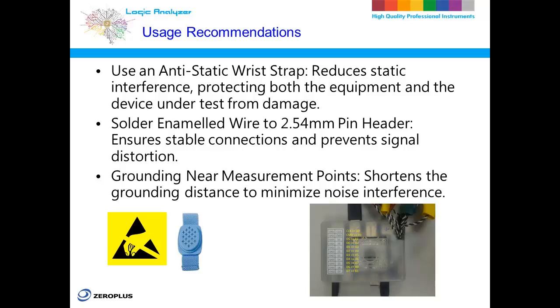Proper grounding is crucial for ensuring signal accuracy and measurement stability. The length of the ground wire and its stability of contact directly impact the quality of the signal. When the ground wire is too long, it increases ground impedance, which can introduce extra noise and affect measurement accuracy. Therefore, it's important to place the ground point as close as possible to the measurement point to minimize unnecessary long-distance transmission and noise introduction. If the grounding point is too far from the measurement point, it can cause unnecessary interference and noise, making it harder to process the signal and leading to less accurate measurements. Grounding should be close to the measurement point to minimize the noise generated by long-distance transmission. Following these usage tips will significantly improve the stability and accuracy of your measurements, while also protecting your equipment from static electricity, unstable signal connections, and improper grounding.